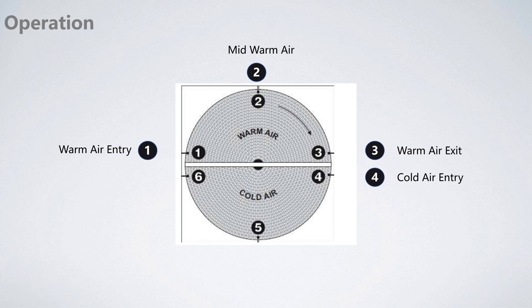The fifth step is mid cold air. Half of the dwell time in the cold air is over. Temperatures at the inlet and at the outlet are about the same. The last step is cold air exit. The air channel has gone through the cold air zone. The storage mass has been severely cooled. Near the inlet, the temperature has almost reached the temperature of cold air.